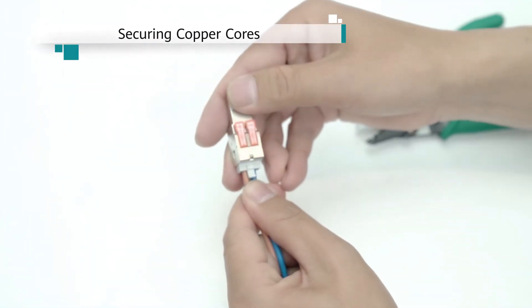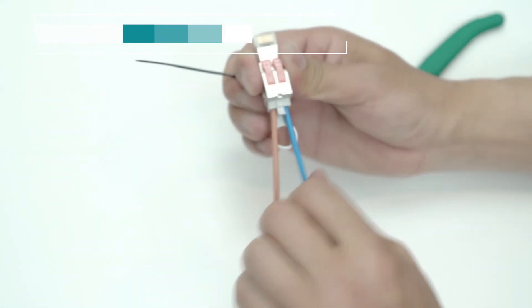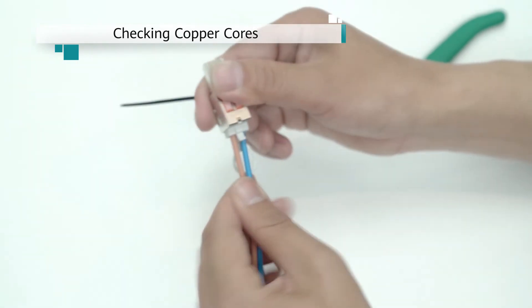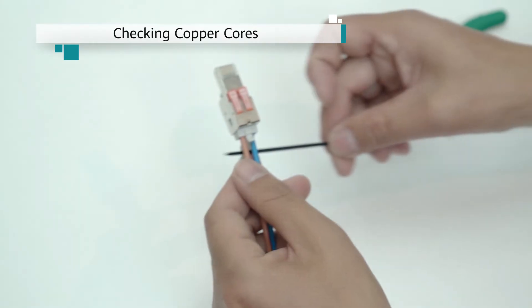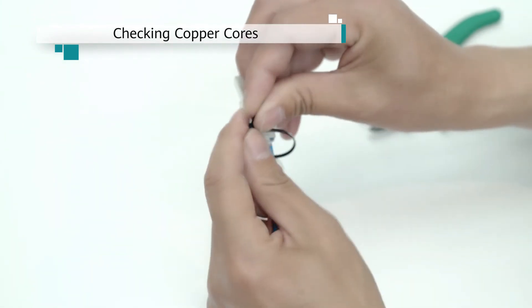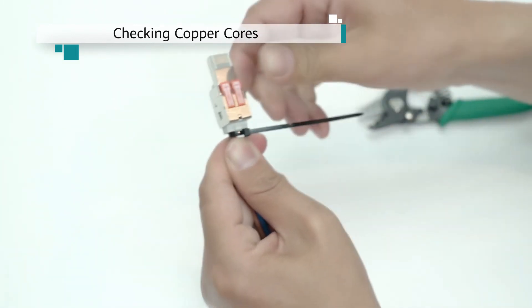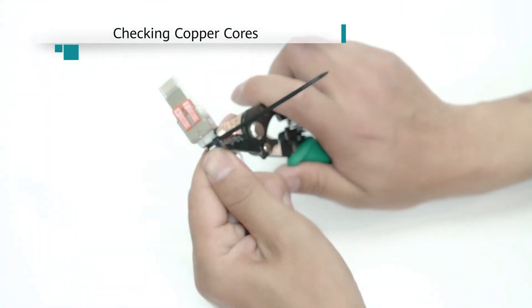Lower the levers and look through the observation windows to verify that the springs do not overlap with the insulation layers. Pull each copper core with a force of about 10 N and ensure that each copper core is properly connected. Bind the copper cores with cable ties in the same direction and cut off the excess cable ties.